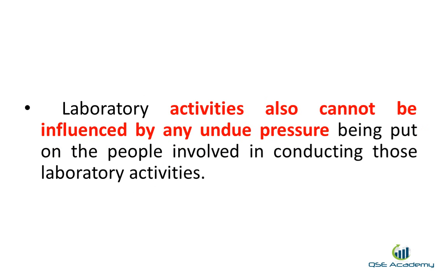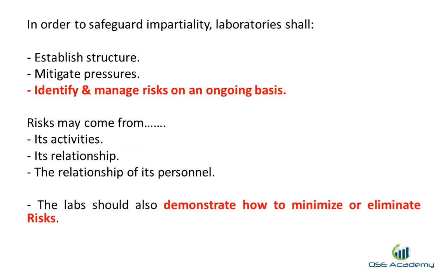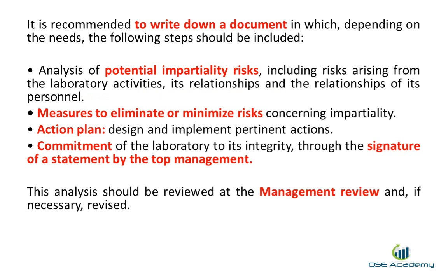Laboratory activities also cannot be influenced by any undue pressure being put on the people involved in conducting those laboratory activities. In order to safeguard impartiality, laboratories shall establish structure, mitigate pressures, identify and manage risks on an ongoing basis. Risks may come from its activities, its relationships, the relationships of its personnel. The labs should also demonstrate how to minimize or eliminate risks. It is recommended to write down a document in which, depending on the needs, the following steps should be included.